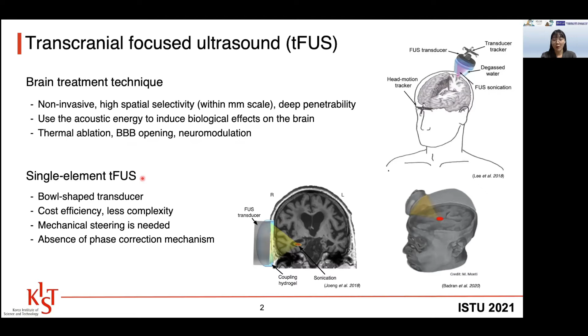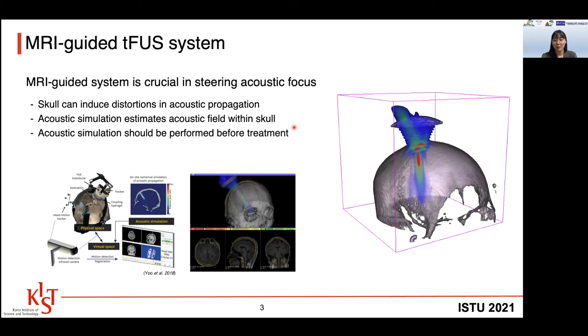neuromodulation. A single element transducer is a TFUS treatment configuration which is relatively cost efficient and less complex, but it needs mechanical steering due to the absence of a phase correction mechanism. An MRI-guided system is crucial in steering the acoustic focus of a single element transducer. Since the skull can induce distortions in acoustic propagation due to a large mismatch of acoustic properties, the guidance system requires acoustic simulation. It estimates the acoustic field within the skull and should be performed before the treatment.